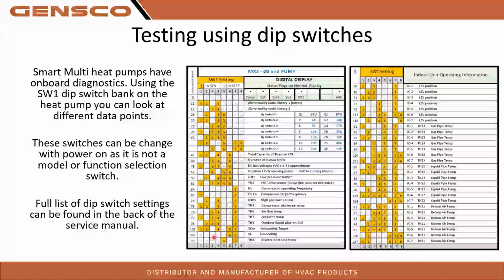So three clears the error code. You're right, switch 2 is for clearing your connection history, for clearing your indoor units if you mess up the addressing. Now, I don't know if you mentioned this: if you set incorrect addressing and you have to change it, addressing is set with the power off.